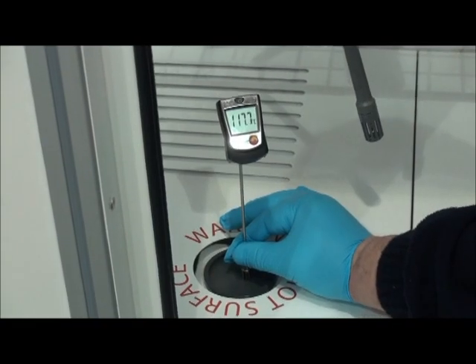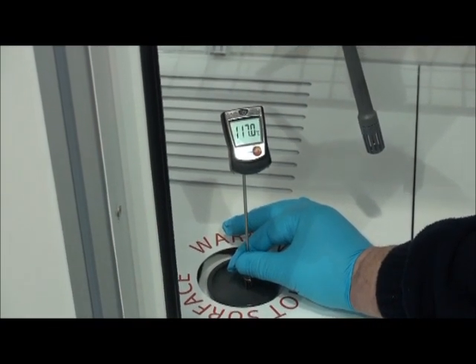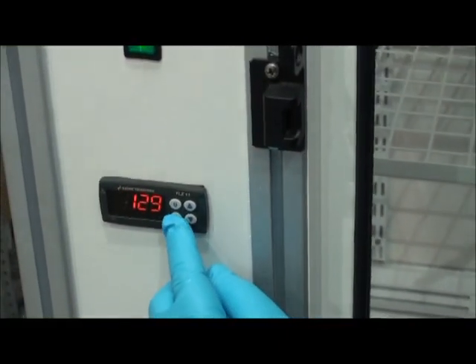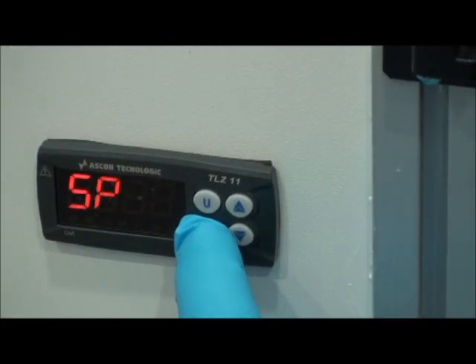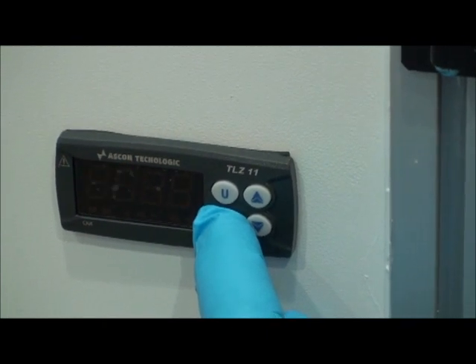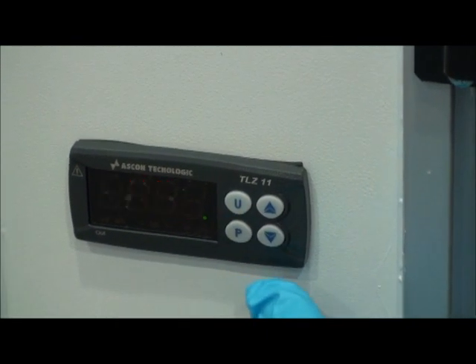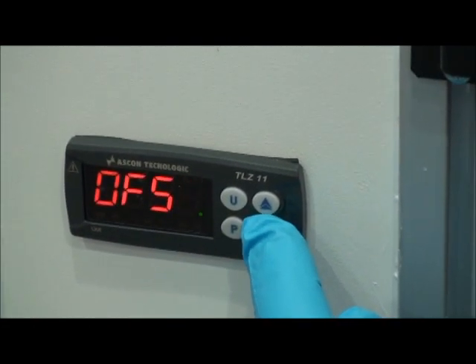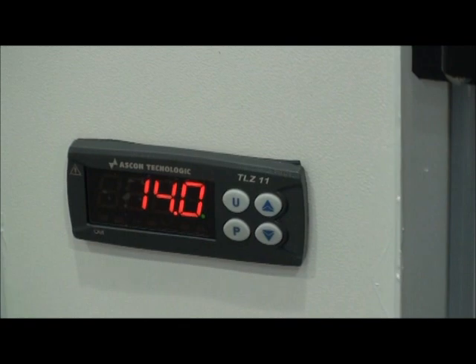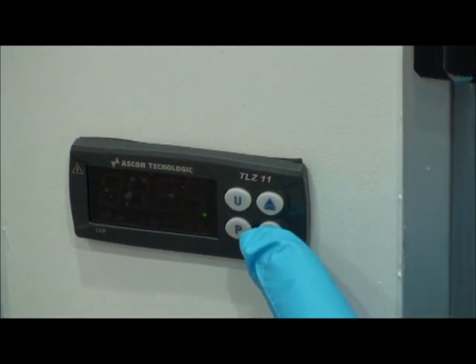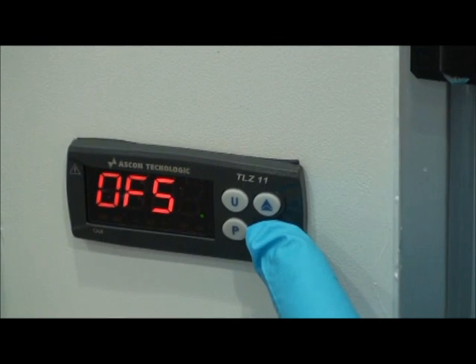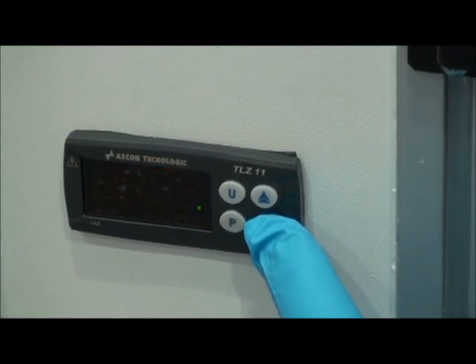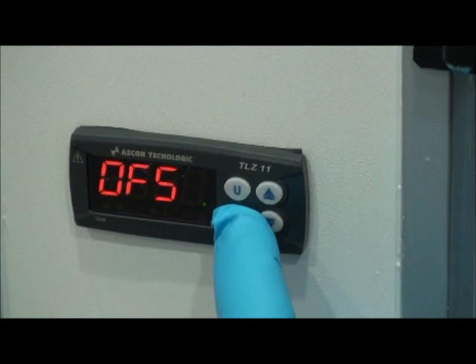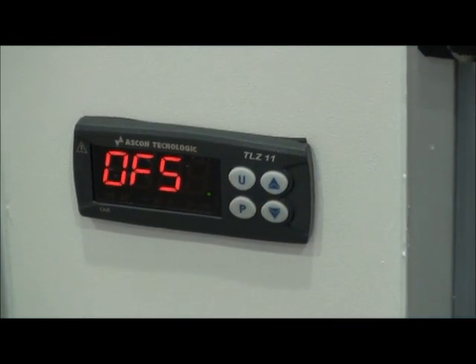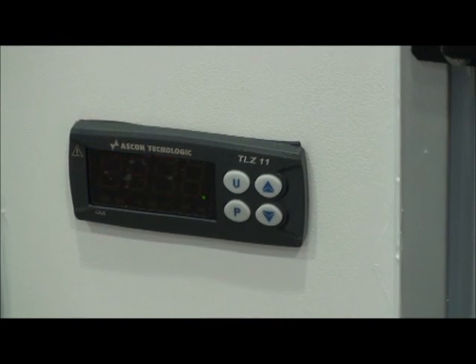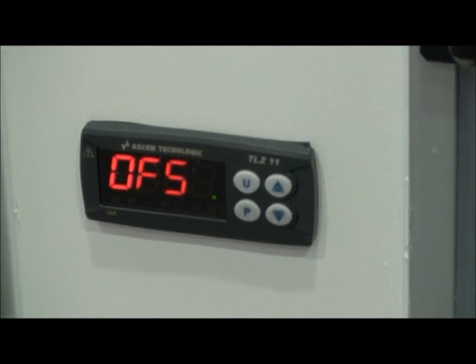To set the offset, first of all you measure the average temperature on the hot plate, and then you go to the control, you hold the P key for more than 5 seconds, and you're into the menu. You scroll down to the offset and you accept, and then you set the offset to the desired value. On this occasion it's 14. To accept, you press the P, and then the display will flash for about 15 seconds, and then it will display the temperature.